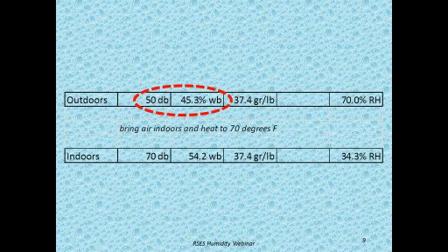That says percent. Sorry about that. That's a typo I didn't catch. That's 45.3 degrees Fahrenheit wet bulb. Well, that air sample, we've got 37.4 grains of moisture per pound of air. That's 37.4 grains. That then gives me a relative humidity of 70%.